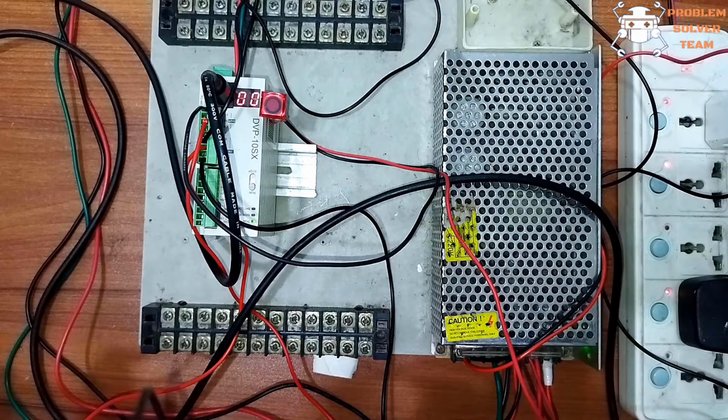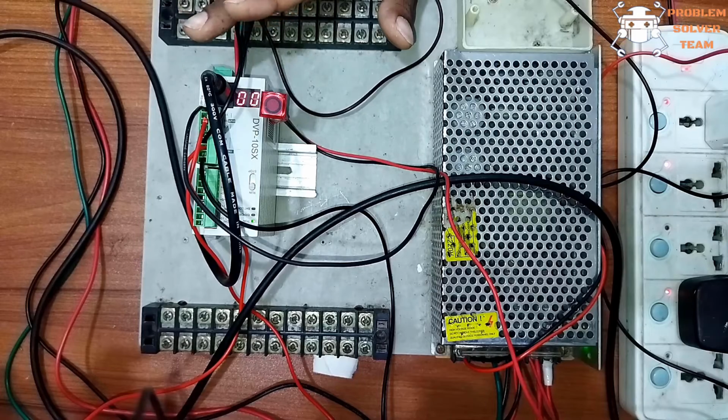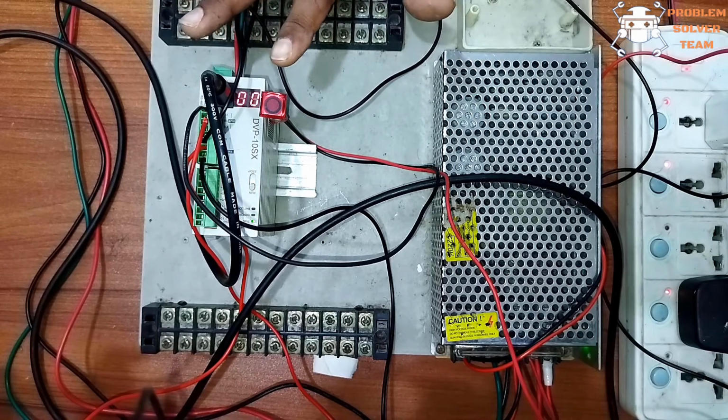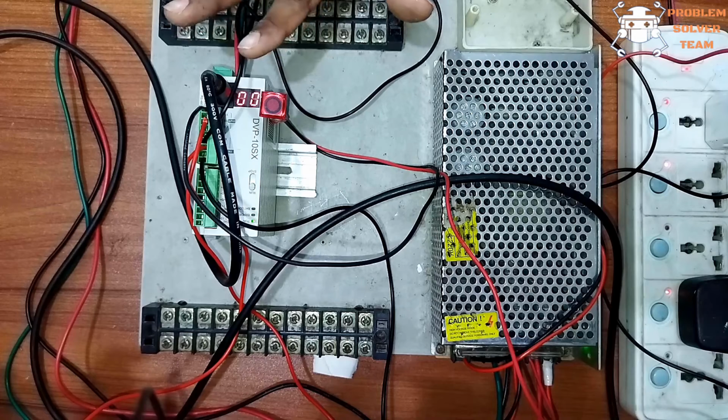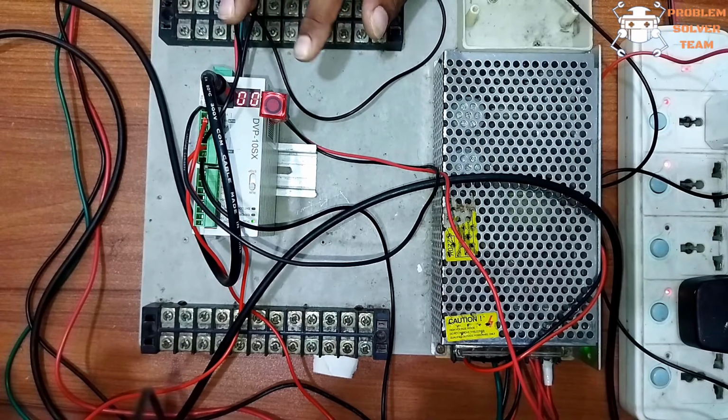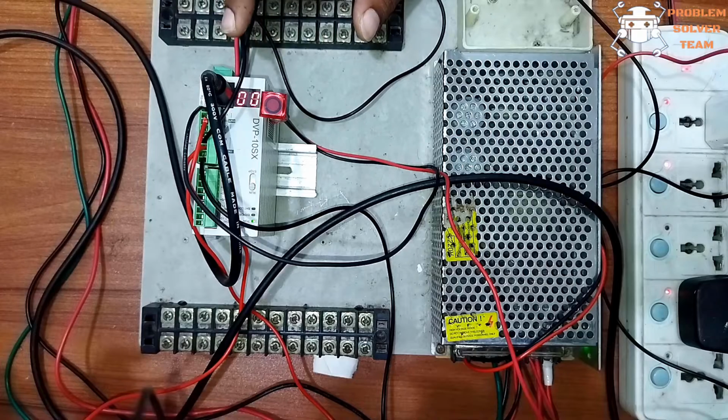Today we are going to start the set and reset instruction. In this diagram, when I press X1, Y1 will be on, and after that, if you press X2, Y1 will be off. The question may come to your mind: what are the set and reset commands? The set command latches this circuit with one press, and the reset command turns off the system with a press of this circuit.